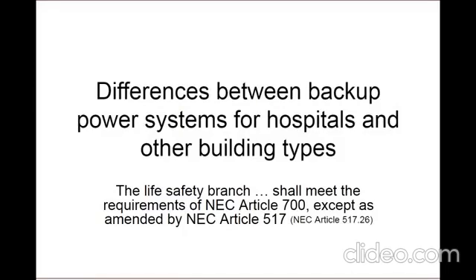So the essential electrical system for hospitals in a way loosely parallels the emergency and legally required standby systems used in other buildings. NEC 517.26 indicates that the life safety branch of the essential electrical system shall meet the requirements of Article 700, except as amended by Article 517. NEC Article 517 takes things a step further and contains more prescriptive requirements, including detailed lists of loads, as Dana mentioned, that may be connected to each system, as well as stricter wiring methods. Next, we'll take a look at some of the differences between NEC 517 and 700.